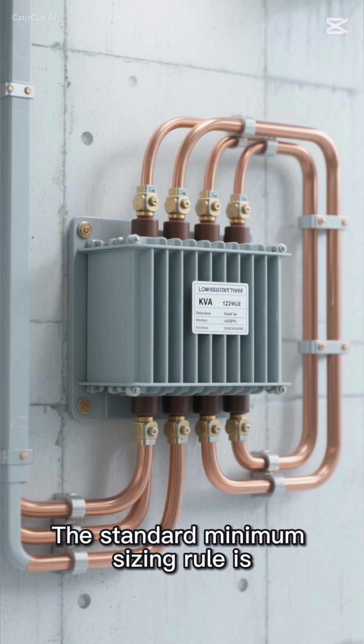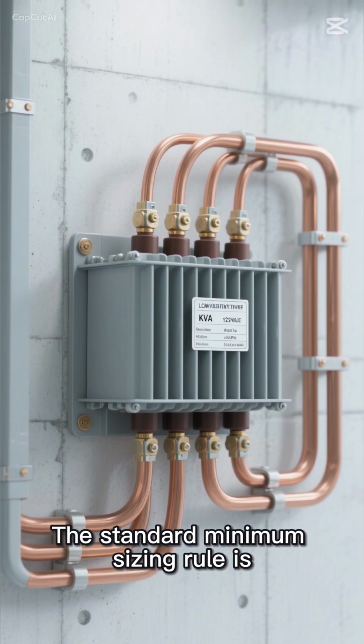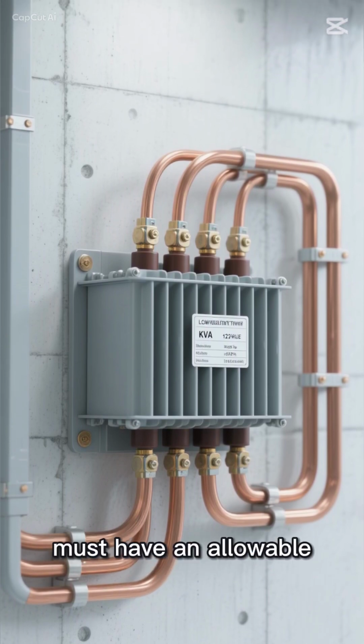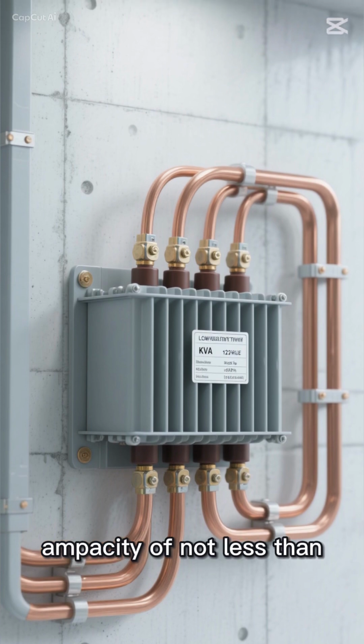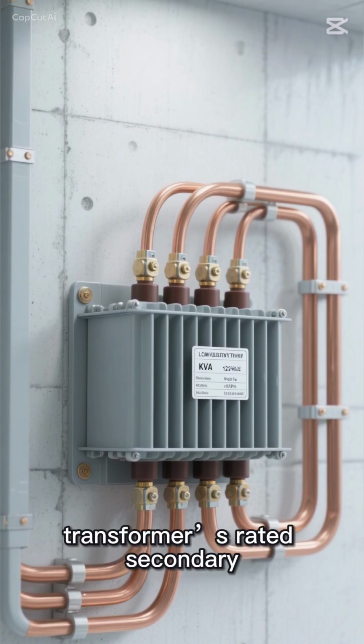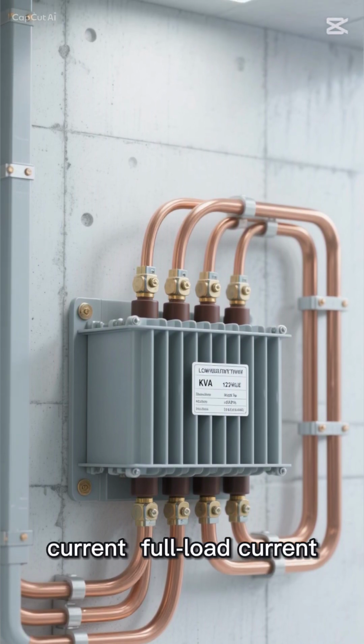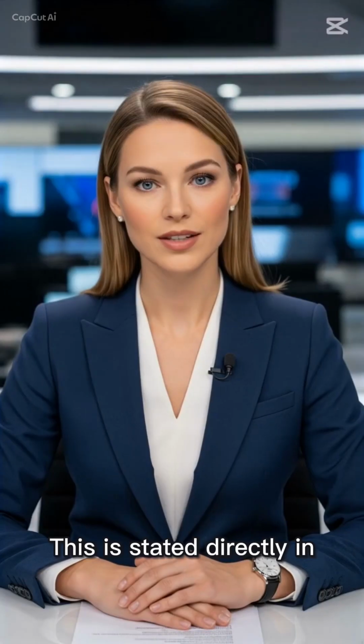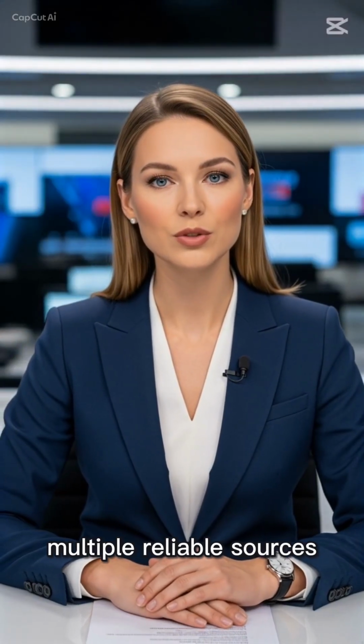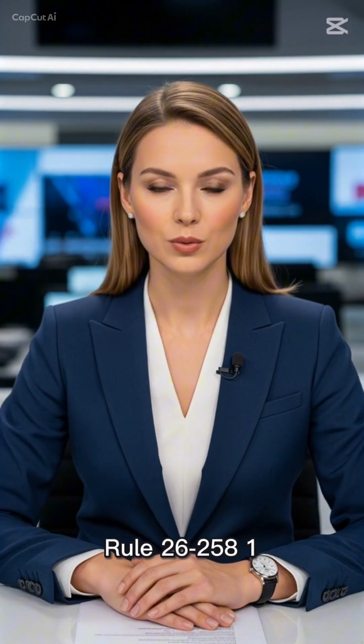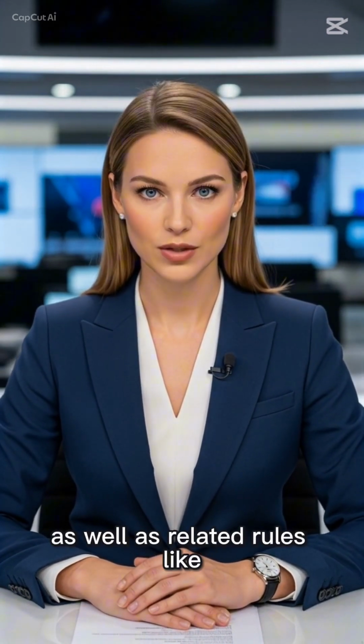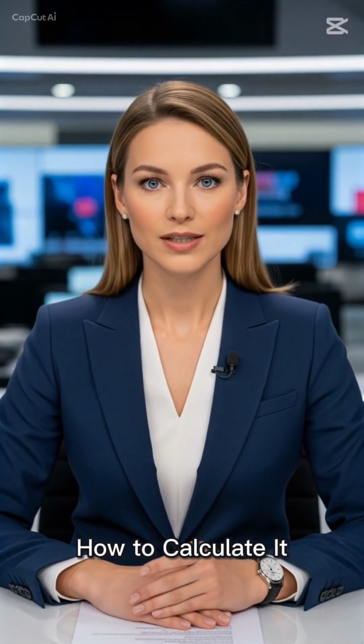26-258, conductor sizing. The standard minimum sizing rule is: transformer secondary conductors must have an allowable ampacity of not less than 125% of the transformer's rated secondary current, full load current. This is stated directly in multiple reliable sources, referencing CEC Rule 26-258 subrules 1 and 2, as well as related rules like 26-256. How to calculate it?